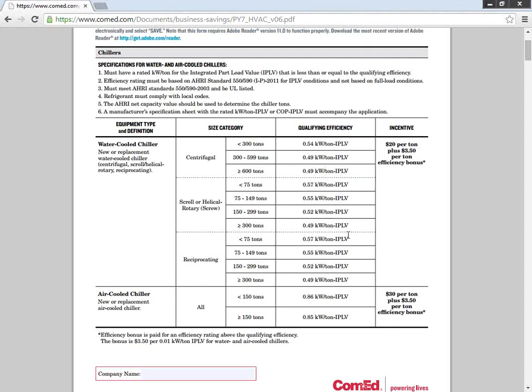You'll note that all these are IPLV, which is the part load efficiency. There are no requirements for full load efficiency, because ComEd recognizes you almost never run at full load, so part load is where the action is. But you have to know what kind of compressor you have, centrifugal, screw, or recip. Centrifugal or screw would be the two main types, and then the tonnage range, to find out what your target is going to be.